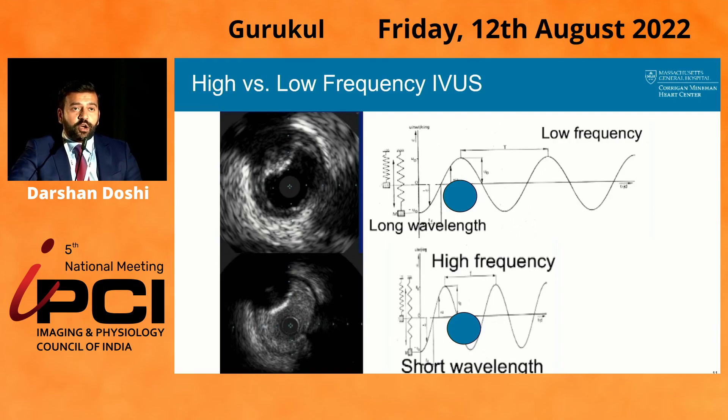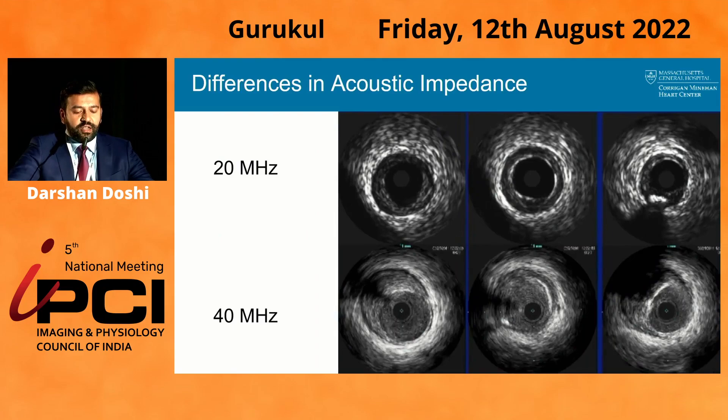However, this comes at a cost. When you start bouncing off of things, you lose penetration power. With the 20 MHz transducer you can see farther out — there's greater penetration. Compared to the higher-frequency IVUS, there is lower penetration, and you're less likely to see the adventitia and beyond.